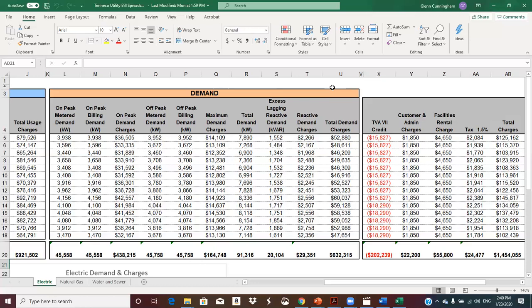I'd say that the bigger the rate, the higher, the better the power factor has to be. On the smaller rates, like that GSA 3, it was 85%. This is a bigger rate, a bigger customer, and they're holding them to a 95% threshold. There are places in the country where it's 97.